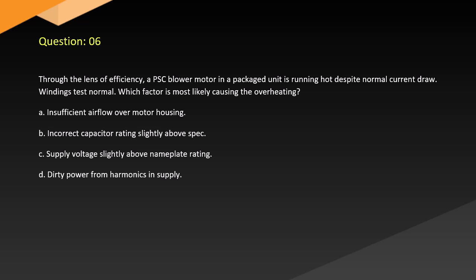Question 6. Through the lens of efficiency, a motor in a packaged unit is running hot despite normal current draw. Windings test normal. Which factor is most likely causing the overheating? A. Insufficient airflow over motor housing. B. Incorrect capacitor rating slightly above spec. C. Supply voltage slightly above nameplate rating. D. Dirty power from harmonics in supply.